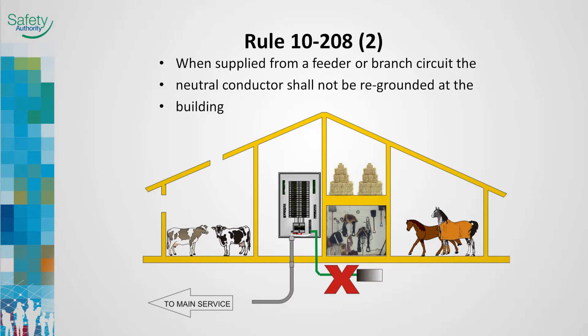Stray neutral voltages are well known to exist and can affect cattle and other livestock in barns and milking parlours. These stray neutral voltages are often referred to as tingle voltage. A tingle voltage problem as small as 0.5 volts can severely affect livestock and result in reduced milk production, skittish or nervous animals, and lack of appetite, all leading to chronic health problems. Regrounding the neutral conductor might contribute to the tingle voltage effect.